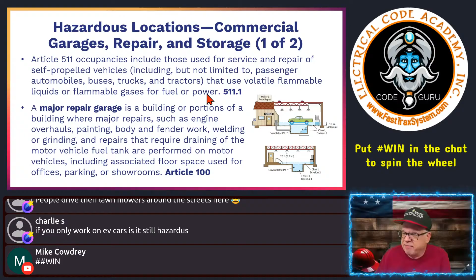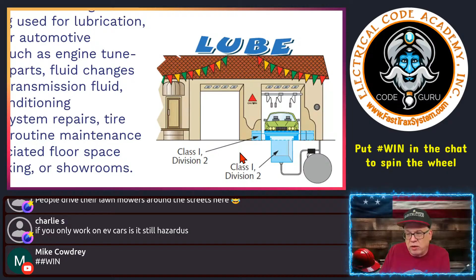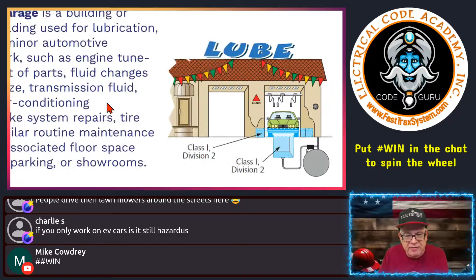All right, so here's the minor repair location, dealing with the same little lube job shop. You've got this area up 18 inches, let's say. Here it'd be a Class 1 Division 2, okay? But the area in the pit down here would also be Class 1 Division 2, because it doesn't have the same volatility as a Class 1 Division 1 location. Very important, and we're not dealing with the same types of liquids. So it's important to understand what you're working in and whether something's classified as a minor repair or a major repair.